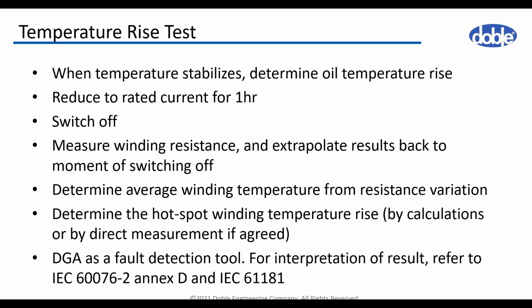Then we measure the winding resistance and extrapolate the results to the moment of switching off. Based on the extrapolated resistance, we determine the winding temperature, and we can also determine the hotspot rise based on calculation or from temperatures measured by sensors embedded in the winding. IEC suggests DGA analysis to be performed before and after temperature rise test, especially for large transformers, as a fault detection tool. And Annex D of the standard is dedicated to detection of localized overheating based on DGA. Some more details could be found in IEC 61181 also.